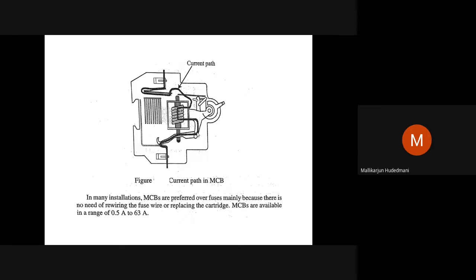One is whenever current flowing through the circuit breaker from lead 1 to lead 2 exceeds the rating. Imagine the circuit breaker is rated for 2 ampere. So 2 ampere current is allowed to flow continuously through this. Why have you provided 2 ampere for a certain application? Suppose your gadget is absorbing 1.5 ampere. Suppose it draws more than 1.5 ampere, definitely there must be a defect in the gadget. It may be a water pumping motor which takes the water from your underground tank to the overhead tank. Let's imagine that the motor got water entry and there is a short circuit in the winding.